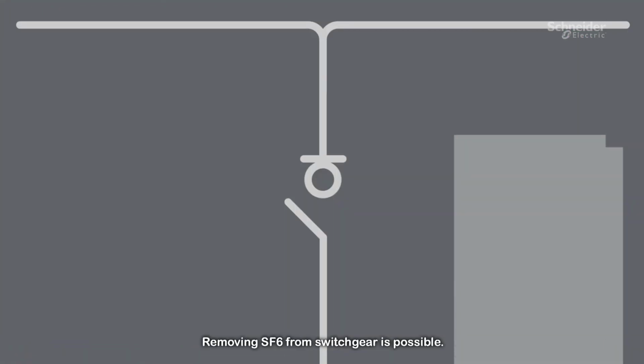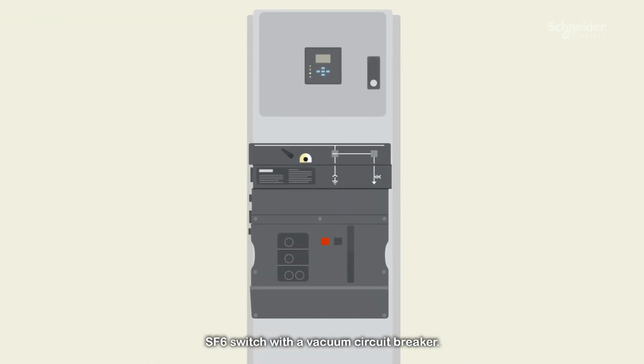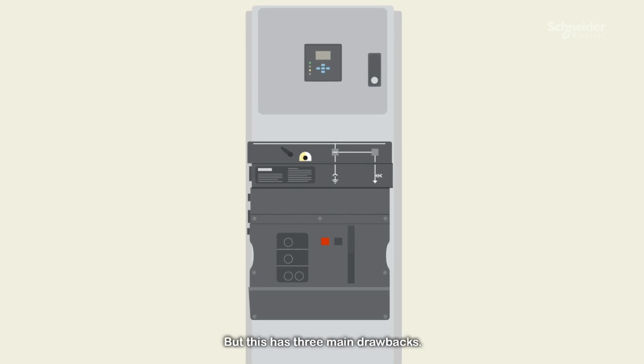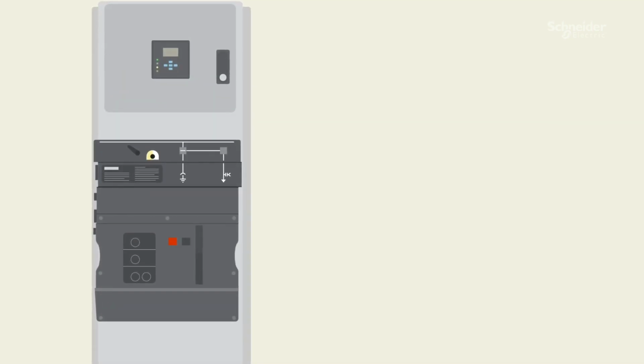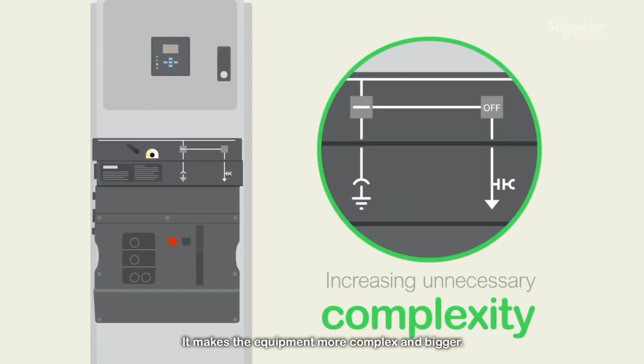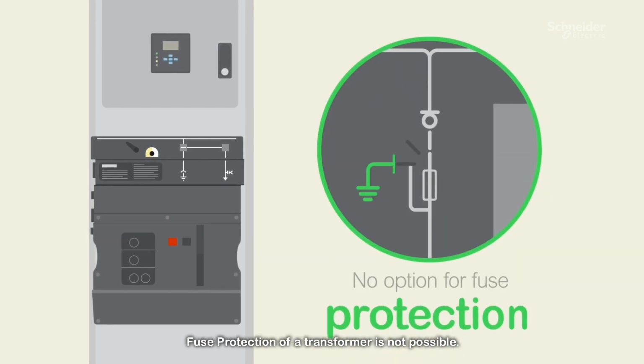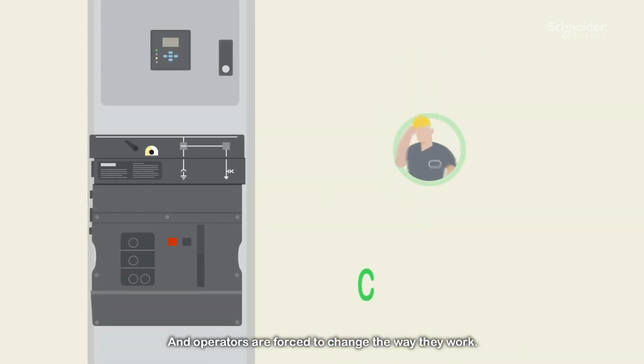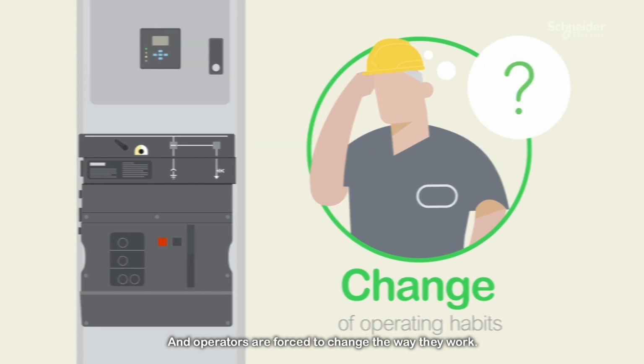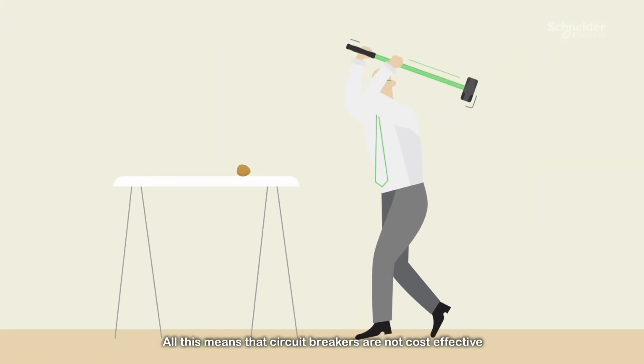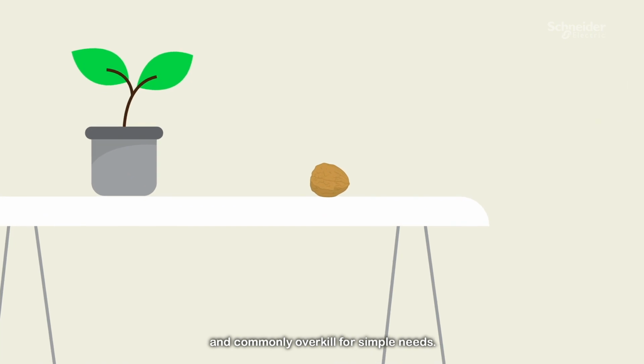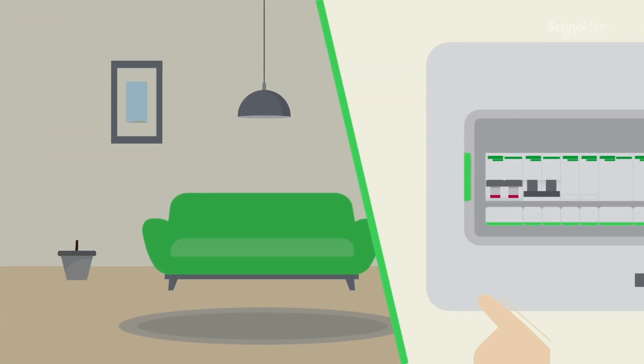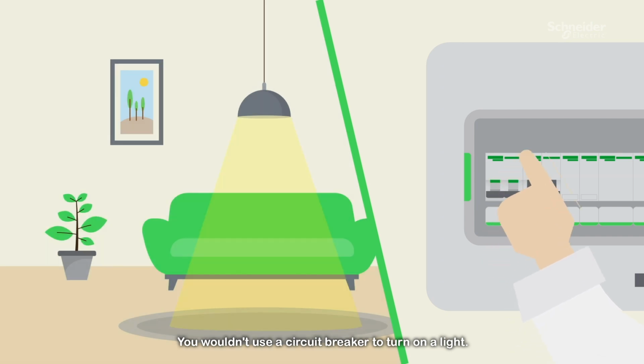Removing SF6 from switchgear is possible. In secondary applications, that often means replacing the SF6 switch with a vacuum circuit breaker. But this has three main drawbacks: it makes the equipment more complex and bigger, fuse protection of a transformer is not possible, and operators are forced to change the way they work. All this means that circuit breakers are not cost-effective and commonly overkill for simple needs. Think of your house: you wouldn't use a circuit breaker to turn on a light.